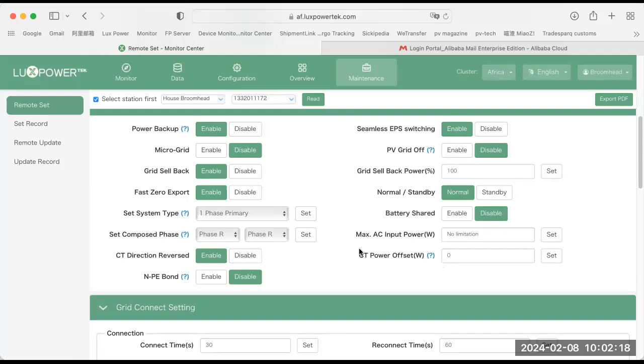I will confirm that. All right, and then on the parallel settings, remember we've gone through that here. If you're doing a parallel setup, you can set it up as a single phase primary or a 3-phase primary, and then obviously your slaves will all be subordinates. Battery sharing, that's especially if you have more than one machine. More than one machine with batteries. I always recommend that you share the battery bank via a common DC bus. Just make sure that your cabling, the lengths of your cables, the internal resistance and all of that is good, so that you can have a shared battery.